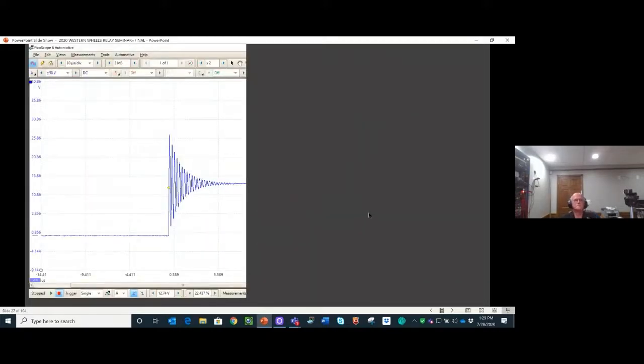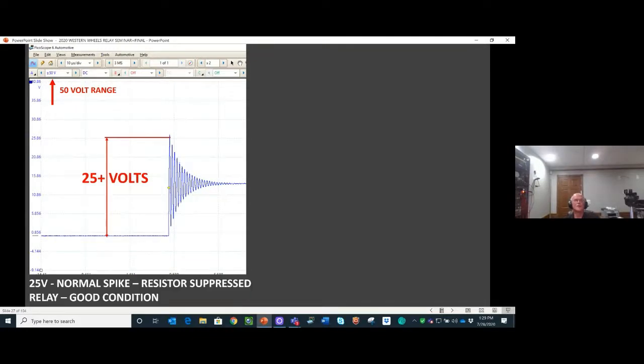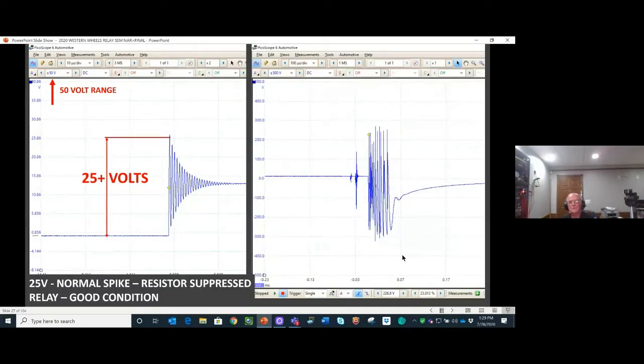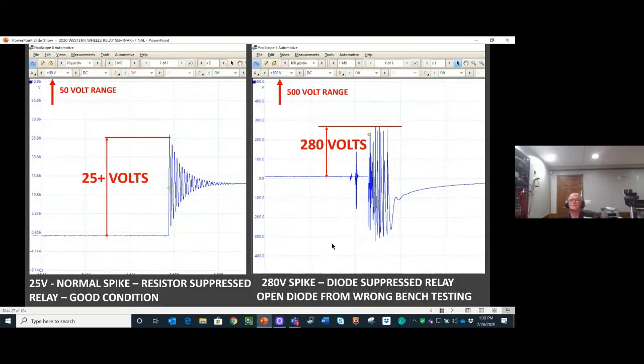Here I hooked up my Pico to a normal coil on a relay, and I'm on the 50 volt range, and I shut off the relay and captured the spike, and it spiked to 25 volts, which is pretty normal. This was a resistor suppressed relay in good condition. 25 volts the system can handle. Now here I've connected it to a diode suppressed relay with a blown diode. I switched my scope to a 500 volt range, and I have a 280 volt spike going out into that circuit, touching PCM modules, whatever it's connected to. And this was a diode suppressed relay with an open diode created by wrong bench testing.